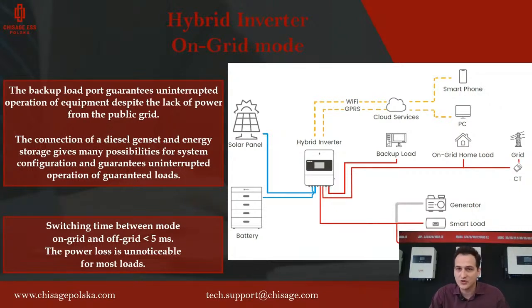If we speak about the hybrid inverter, we have 2 modes. First, on-grid mode. In on-grid mode, we have the grid, the on-grid home load, and we can support the backup load. Also on the GEN port, we can connect a smart load, or we can connect an on-grid inverter, so we can do AC coupling. We can also connect the generator, but it will not work in on-grid mode. In off-grid mode, the generator can be connected, but the inverter will not take power from this generator.